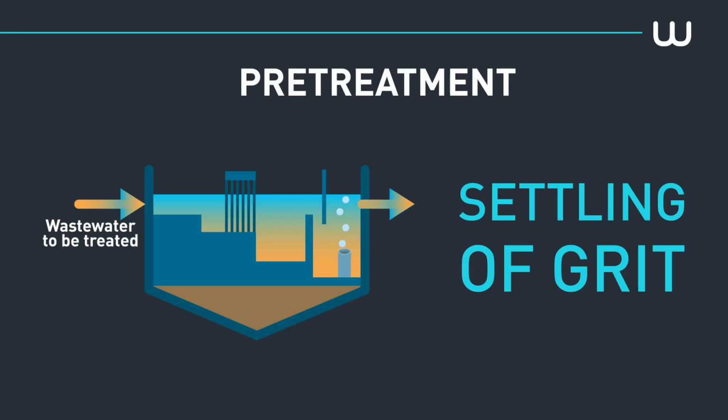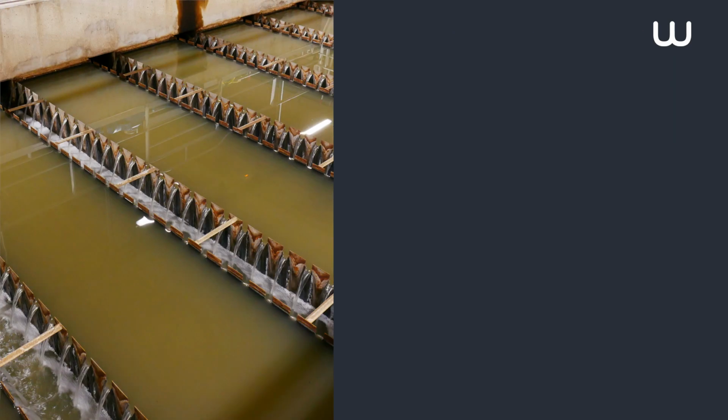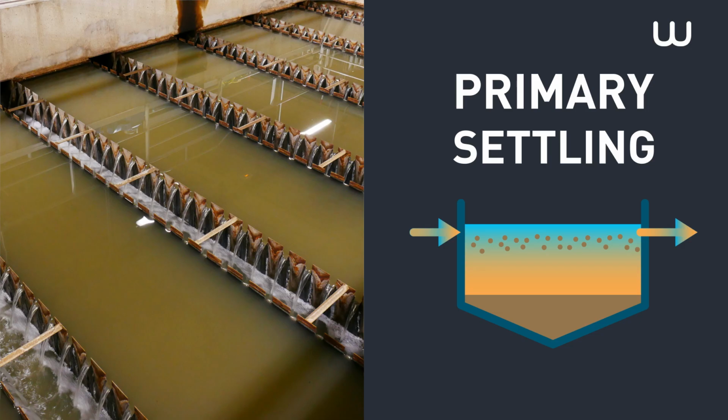effectiveness of wastewater treatment. The purpose of primary settling, sometimes called primary treatment, is to remove suspended solids that are not removed during pre-treatment because they are too small. This settling stage may be preceded by a coagulation flocculation stage, more frequent in the case of urban wastewater treatment than in industrial water treatment.